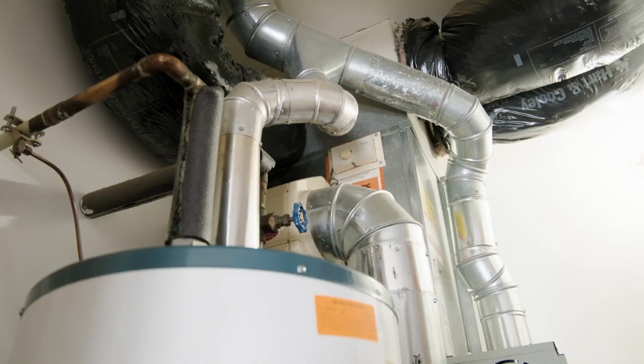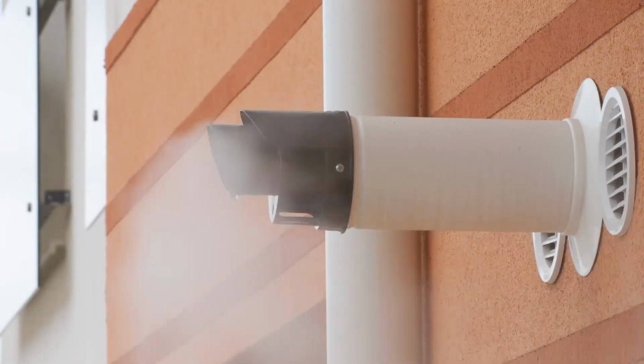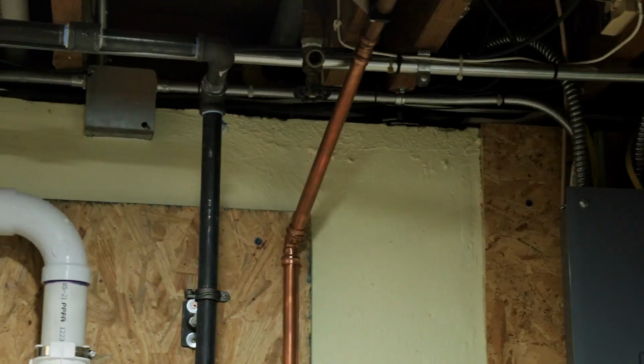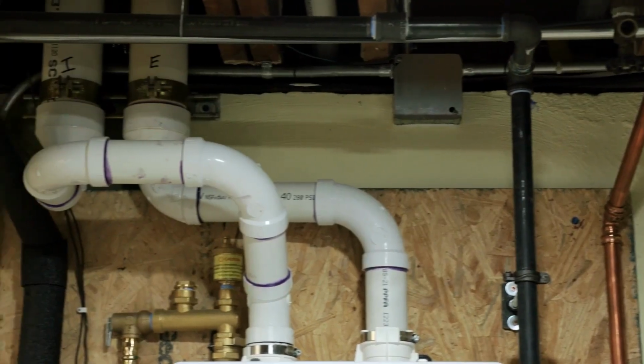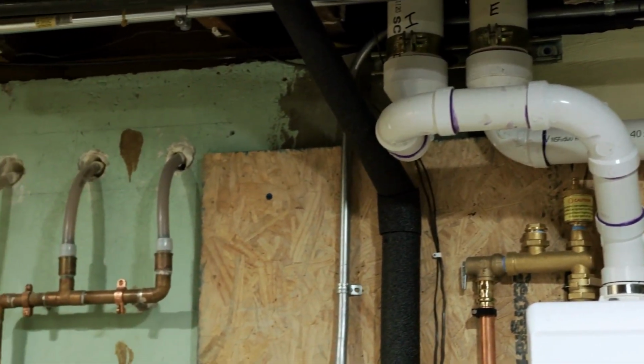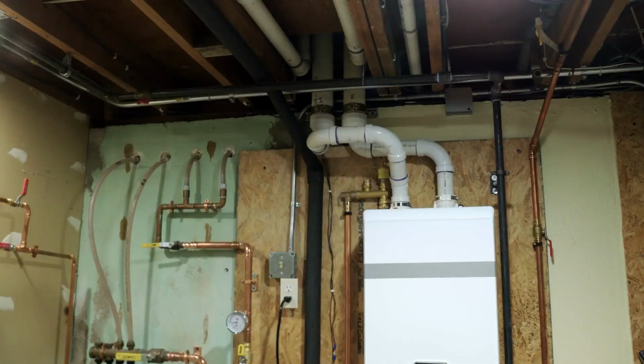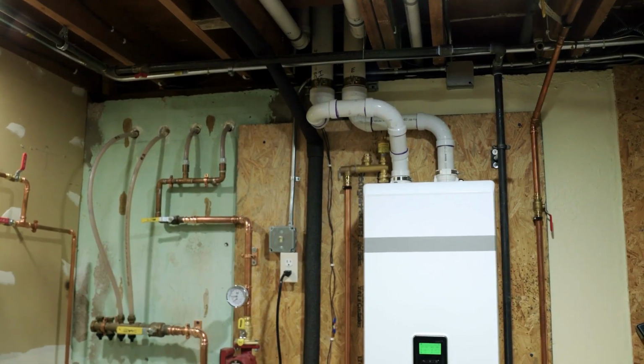Let's talk about ventilation. Does a boiler require ventilation, and are there concerns with that? Older boilers need combustion air from the room to operate. They have just a chimney for the exhaust. If you've done remodels over time, the square footage may have gotten smaller in the room and the combustion air is being suffocated. Newer model boilers will bring in the combustion air from outside, and then the exhaust will go outside too, so you don't have to worry about the square footage. And they also have a tendency to condensate, so you have to have a poly exhaust pipe in order to keep that from corroding. So sometimes the older pipes can't be repurposed.